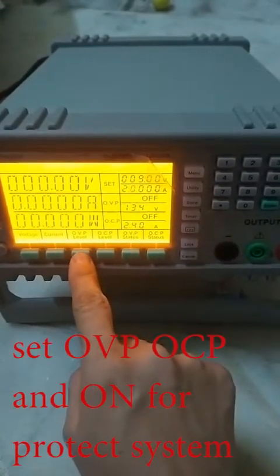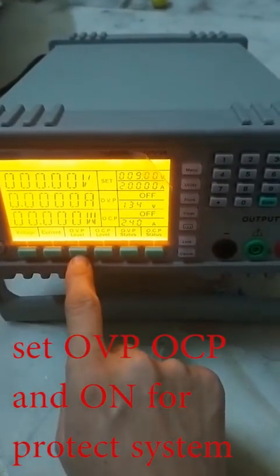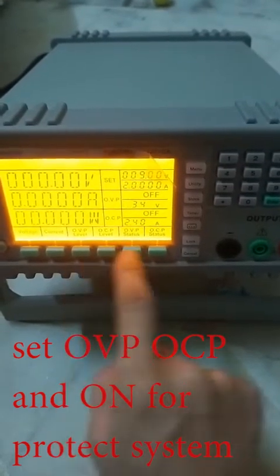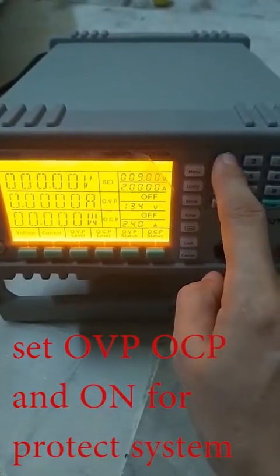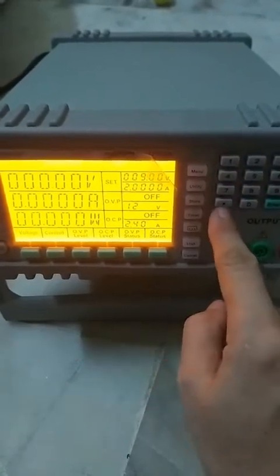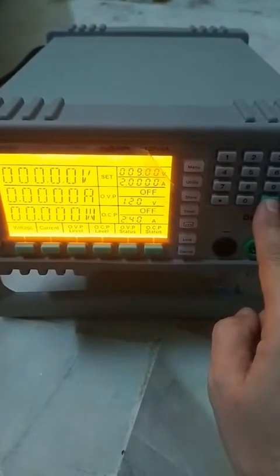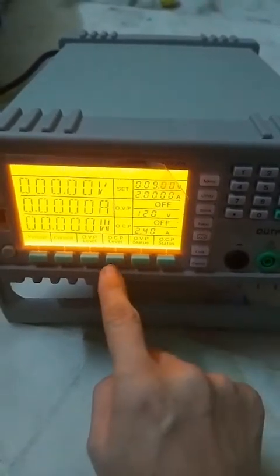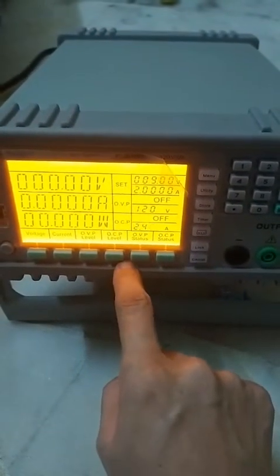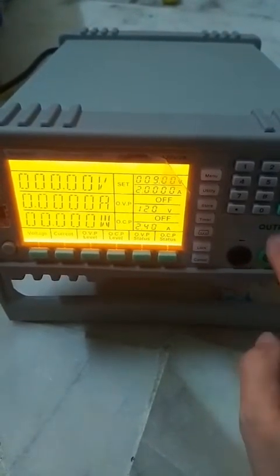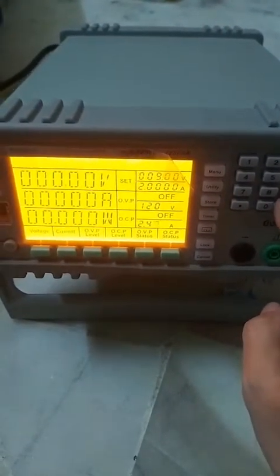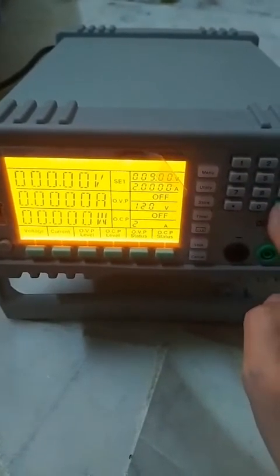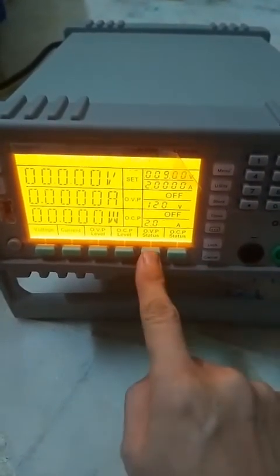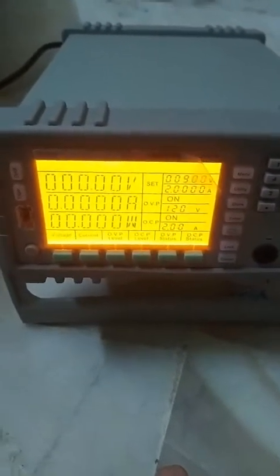Then you click OVP. OVP is over voltage protection. In our case, we can set it to 120, following the maximum value of the power supply. And then we set the OCP, over current protection, and we can set it to 2 amperes. At this moment, you can turn on the protection. If any value goes beyond the setting value, it will stop to protect your DC power supply.